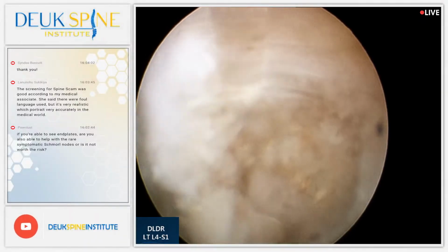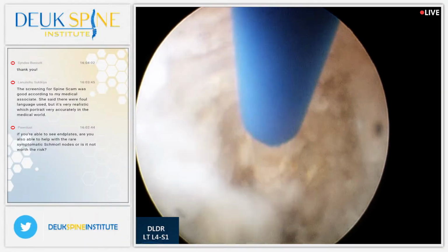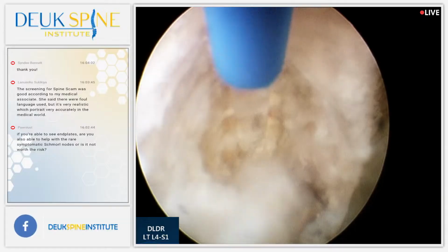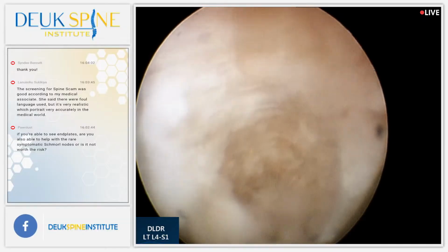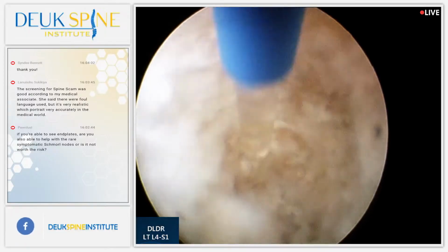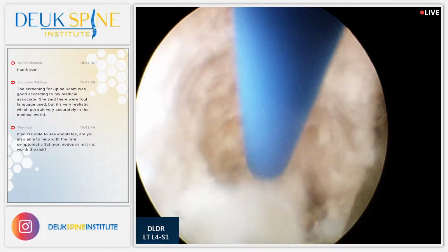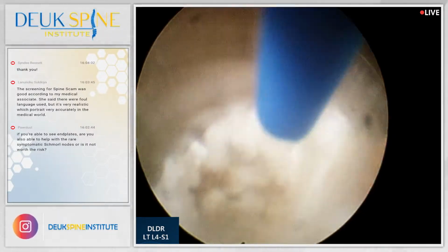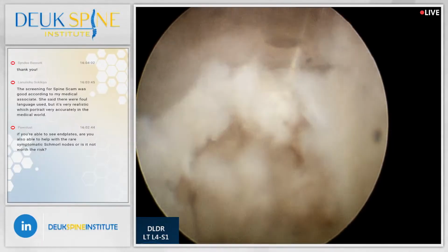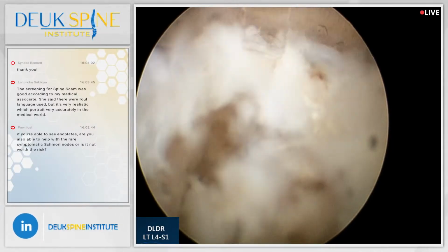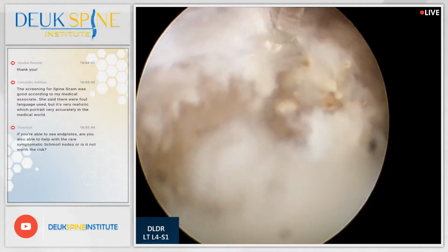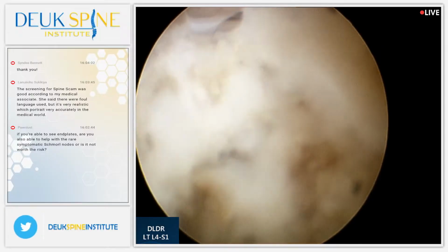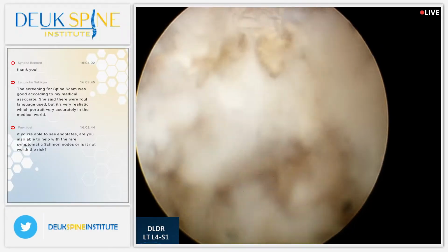At this moment, no current questions. Thank you. We're just about done here. This is another extremely scarred up disc, and it's taken a lot of energy. How much have we dumped into this one? Probably around 40? 28.55. All right, only 29, so it's not as much as I thought. Our last patient took a full 65 joules of energy in one disc on one side. Actually, total on both sides, 120 joules. That was our Russian patient.